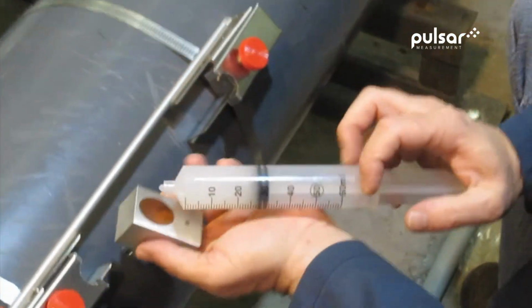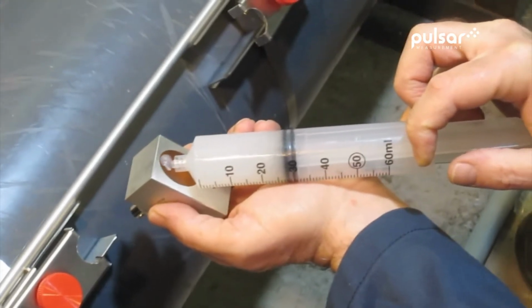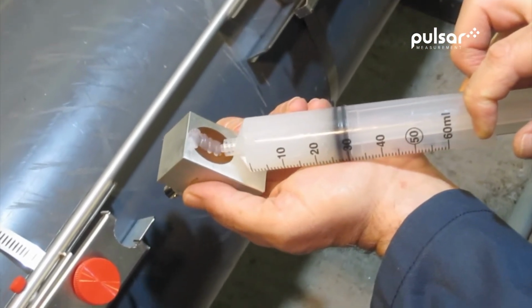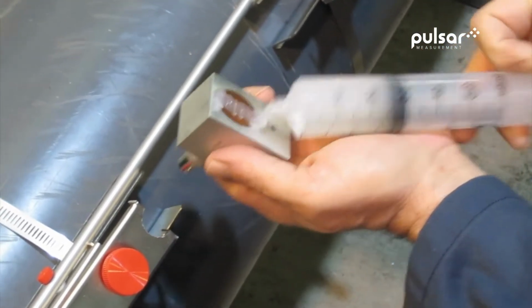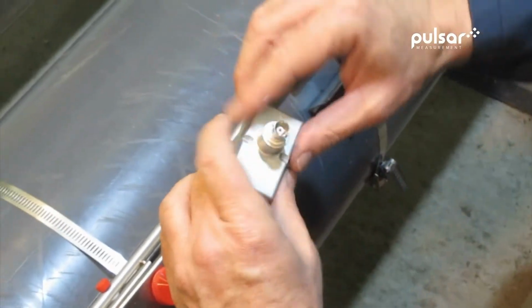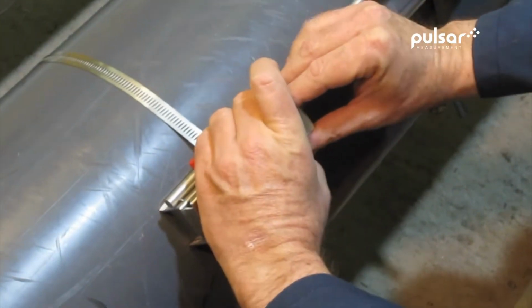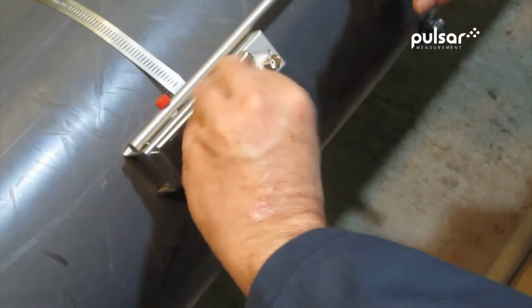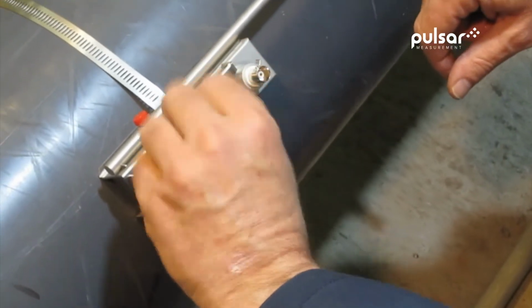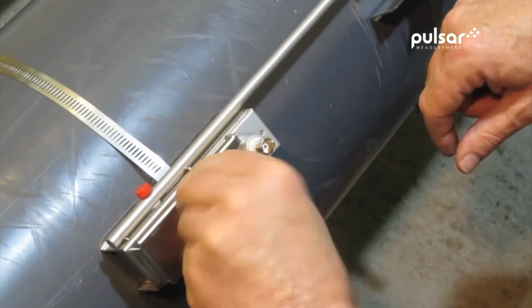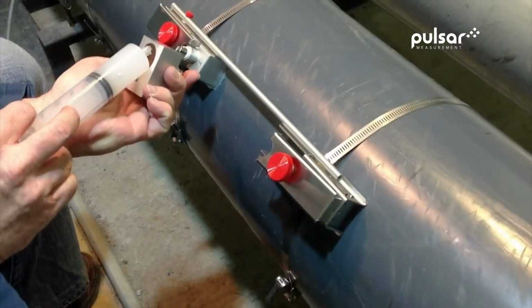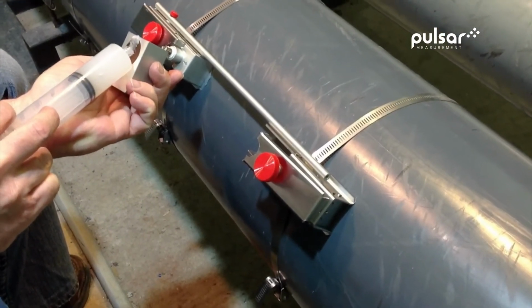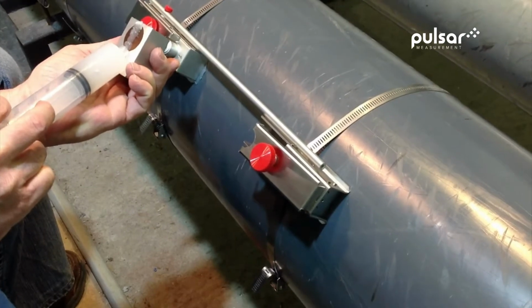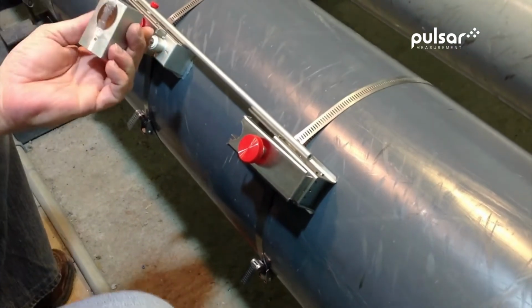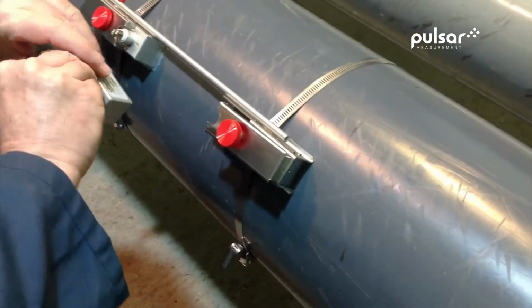Coupling compound is applied to the face of each transducer to help conduct sound efficiently into the pipe. Then we insert the transducer into the mounting bracket and secure in place. Compound is applied and the second transducer is mounted and tightened onto the pipe in the same way.